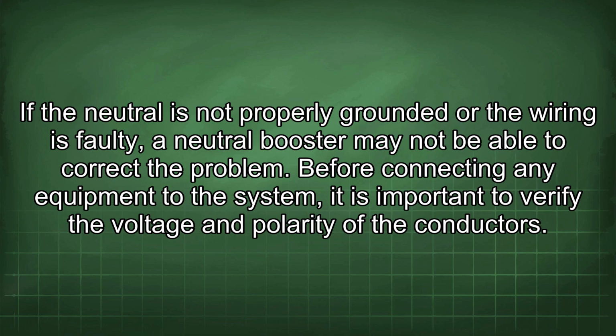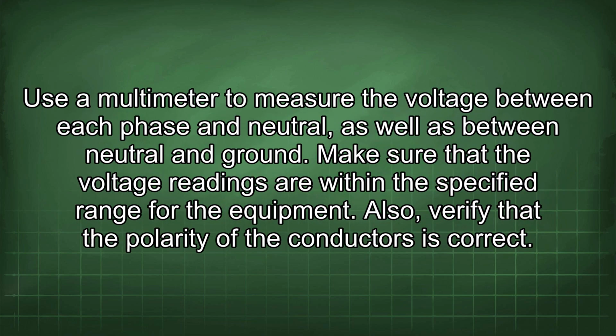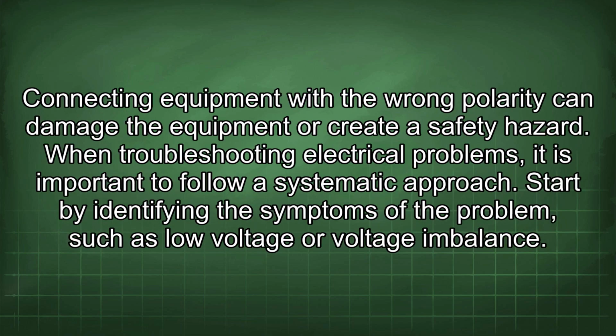Before connecting any equipment to the system, it is important to verify the voltage and polarity of the conductors. Use a multimeter to measure the voltage between each phase and neutral, as well as between neutral and ground. Make sure that the voltage readings are within the specified range for the equipment. Also, verify that the polarity of the conductors is correct. Connecting equipment with the wrong polarity can damage the equipment or create a safety hazard.